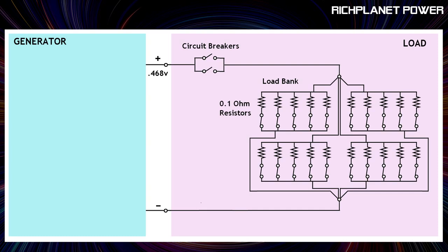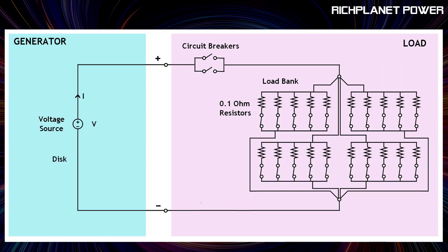Each of the 20 resistors, for example, has a 30 amp switch so that the resistor can be turned on or off, 30 amp rated I mean. Switches, when closed, have a finite contact resistance, which adds to the overall resistance of the circuit. Now, if we consider the equivalent circuit, the generator produces voltage V and a current I, which runs through the disc, across the brushes, through cables, through two large parallel wired switches, then into the load bank, and back through another set of brushes, onto the rotor and back to the disc.